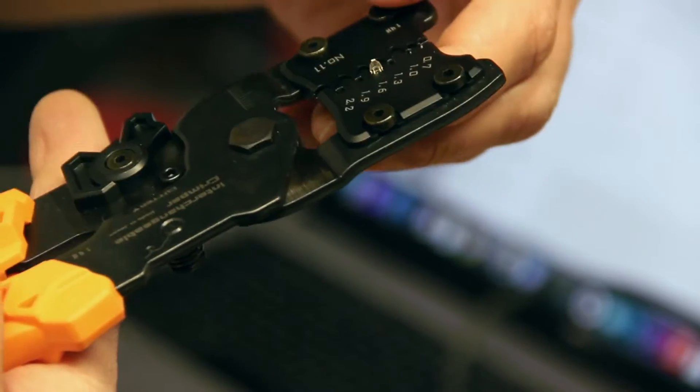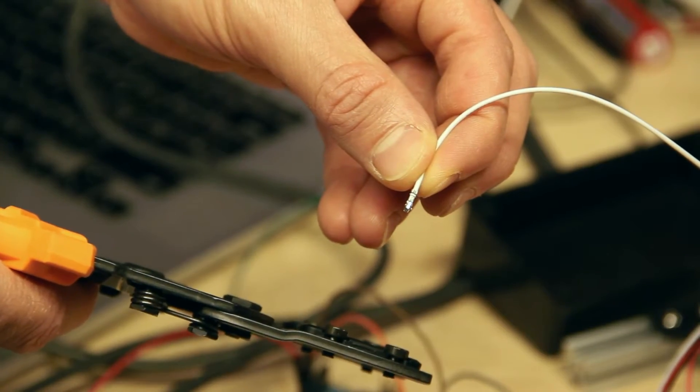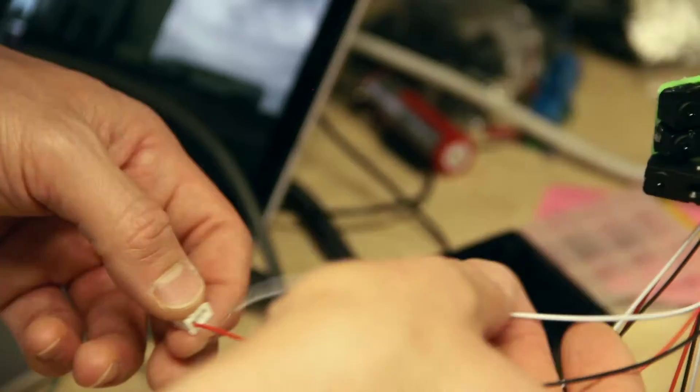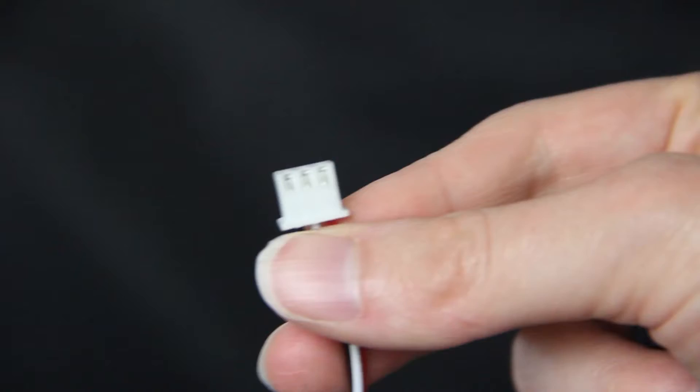Care should be taken when crimping to ensure a good electrical connection. You can pull on a crimp slightly to make sure that it's snug before you insert it into the connector housing, and a small pull can also be given once it's in the housing to make sure it's locked.